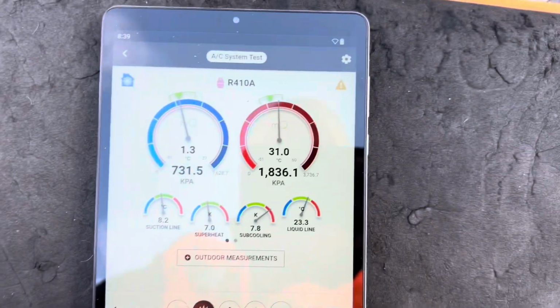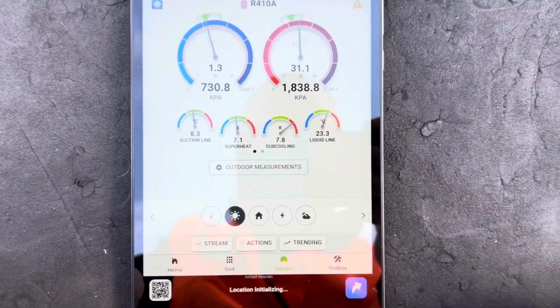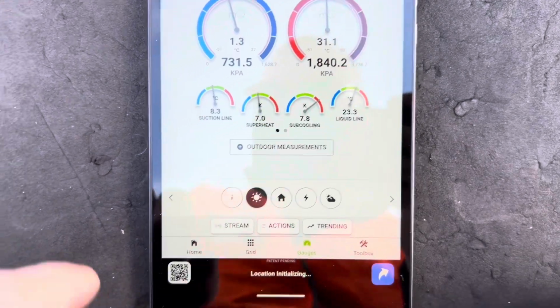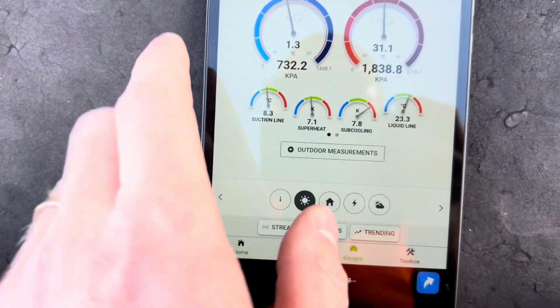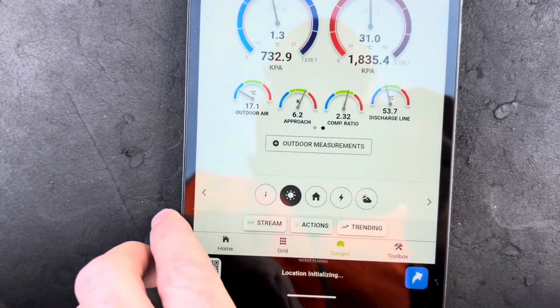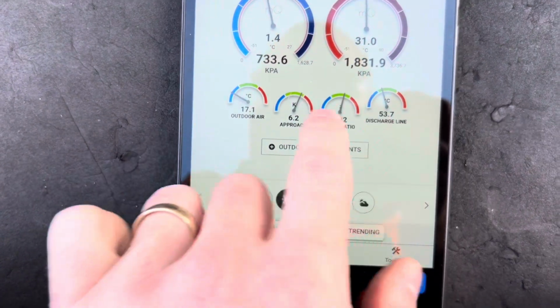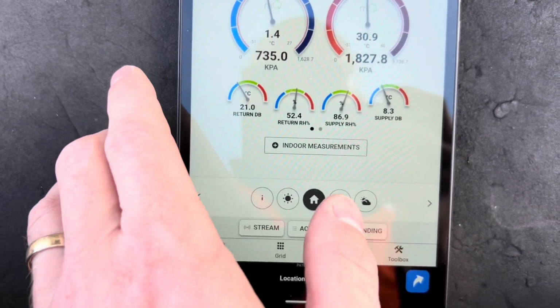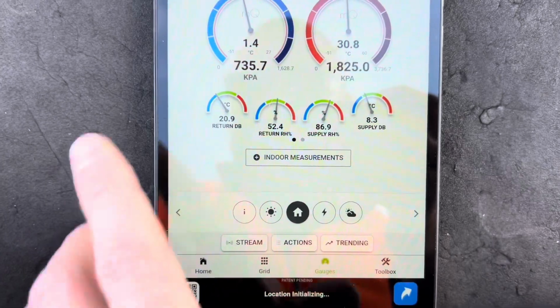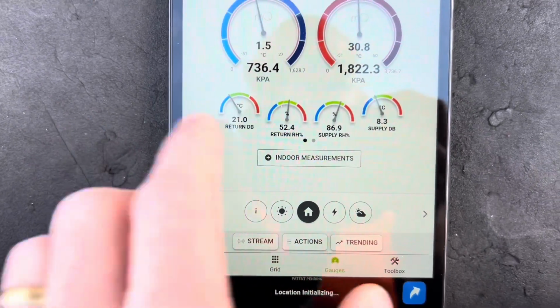So it's been running for about 10 minutes now, and everything's looking pretty good. Superheat's nice, subcooling's nice, discharge temp's alright, supply air 8.3, returns dropped from 24, 25 or whatever it was, so that's looking pretty good.